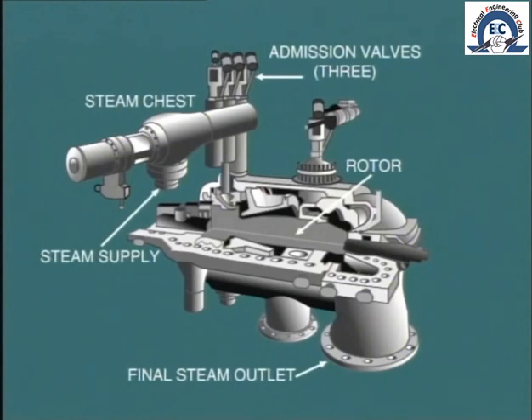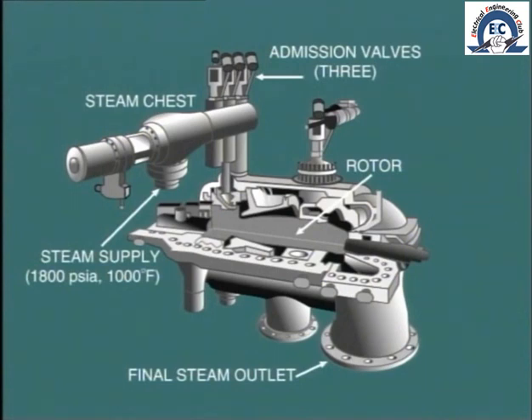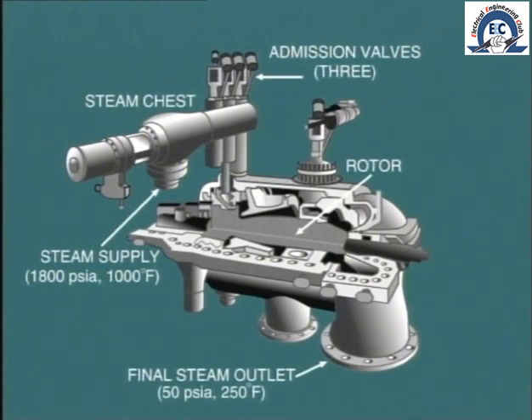How it actually functions and produces power. As we all know, steam at high pressure and temperature — say 1800 PSIA and 1000 degrees Fahrenheit — is admitted at one end of the turbine. After passing through the turbine, this steam exits at a much lower pressure and temperature, say 50 PSIA and 250 degrees Fahrenheit, for a typical back pressure turbine.